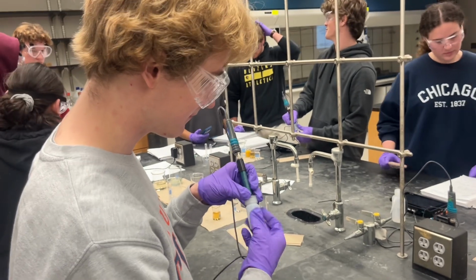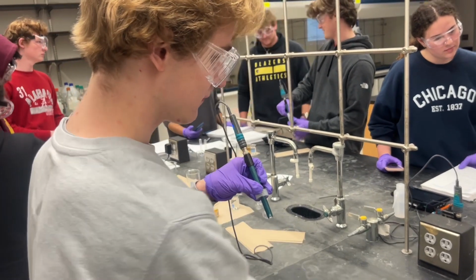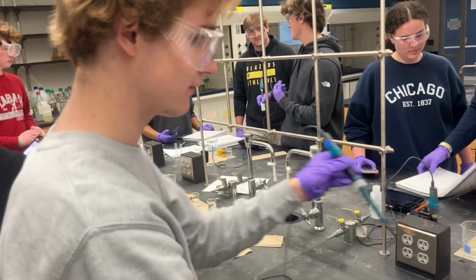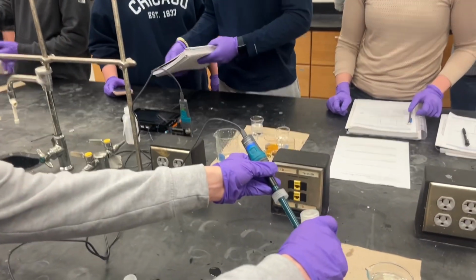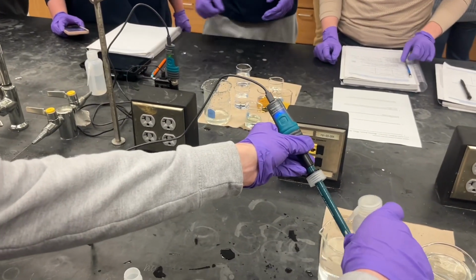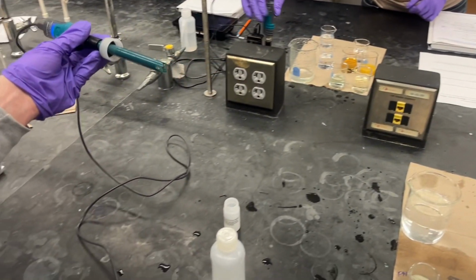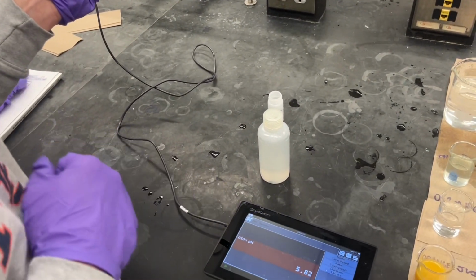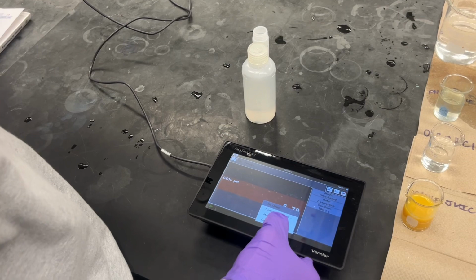To start our pH meter reading lab, we began by calibrating the pH. We started by spraying the probe with distilled water and then placing it in a pH 7 buffer solution. On our tablet, we put in the known value of the buffer solution, which was a pH of 7, and applied it.